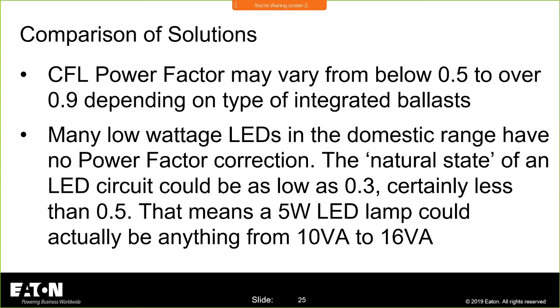Now, here's the issue. We talk a lot about load and energy savings from things like compact fluorescent and LED lighting. If you're in some of these industrials where you get billed for power factor, there's a hidden cost in here that nobody talks about. If you Google power factor and LED or power factor and fluorescent, you'll find IEEE documents and EC&M magazine articles and other similar trade magazine articles on the hidden costs around these solutions, because we make an assumption that our bills are only on watts, where in reality, a lot of our bills, we get penalized for power factor. And what I've learned is that the power factor of a lot of these loads varies.